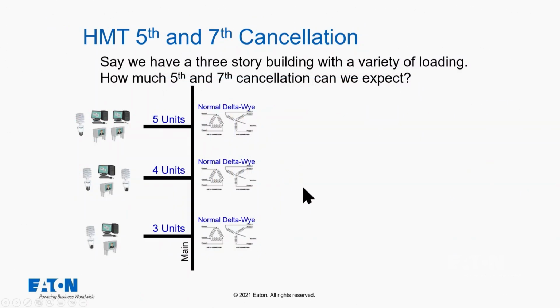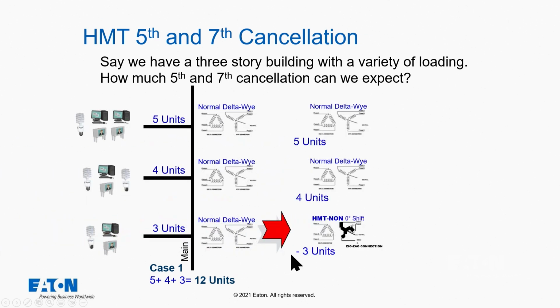But as an example, let's say you had a commercial building and you had a bunch of computer power supplies on each floor. We'll say we have 5 classrooms, 4 classrooms, and 3 classrooms of students with computers. So if you had delta-Y transformers, you add up to a total of 12 units of that fifth and seventh harmonic current. Remember, the third harmonic is going to circulate in the delta, go back to the load. So we don't worry about the third on the primary of these transformers. But on the primary, on this riser bus, we do have to worry about the fifth and seventh. If we phase shifted just one with a harmonic mitigating transformer, we'd have 5 plus 4 minus 3, or 6 units of harmonic current for fifth and seventh. So basically, I've cut my harmonic current in half.